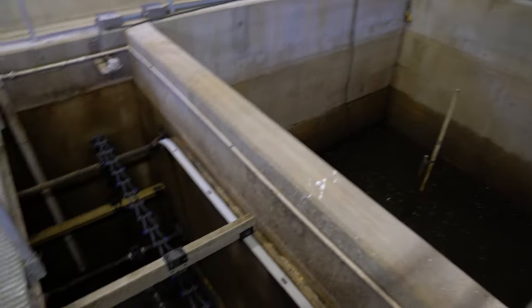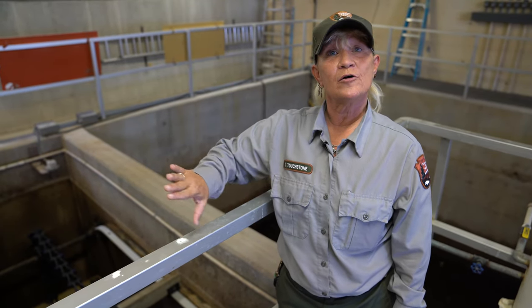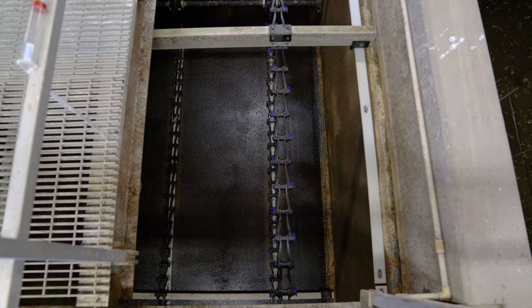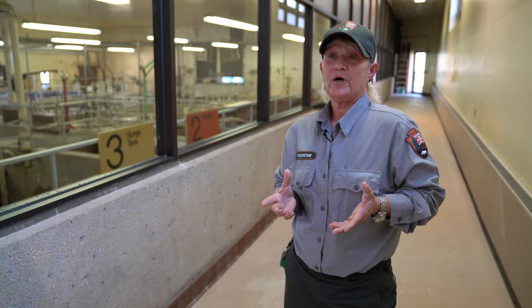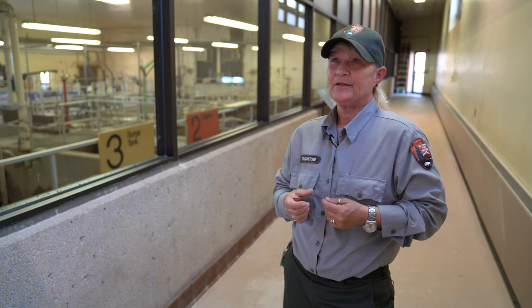Look in here — this is the clarifier. This is where the bugs come after eating and breathing. They settle to the bottom because they're fat and happy. Those flights on these chains run around and around and push all those bugs back over there. This air pump picks them up and sends them right back to the beginning of the aeration tank, where there's lots of air and more importantly lots of food. That's the bulk of what we do as wastewater operators — we're bug sitters. We're highly skilled, technically trained bug sitters, and if we do our job correctly, they do their job correctly.